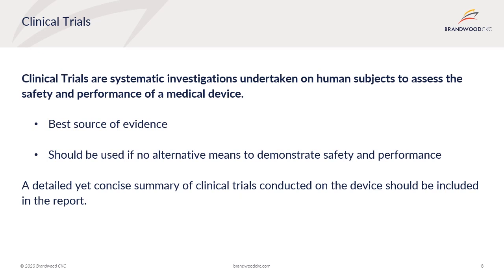It is important to note that a clinical investigation should be planned and conducted where there are gaps in the data available for a medical device that cannot be addressed by other means. This means that if you do not have sufficient safety data and you cannot use literature or post-market data to prove this, then you may need to conduct a clinical investigation.